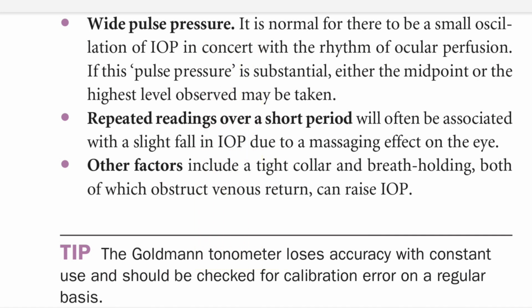Wide pulse pressure. It is normal for there to be a small oscillation of IOP in concert with the rhythm of ocular perfusion. If this pulse pressure is substantial, either the midpoint or the highest level observed may be taken. Repeated readings over a short period will often be associated with a slight fall in IOP due to a massaging effect on the eye. Other factors include a tight collar and breath holding, both of which obstruct venous return, can raise IOP. Tip: the Goldmann tonometer loses accuracy with constant use and should be checked for calibration error on a regular basis.